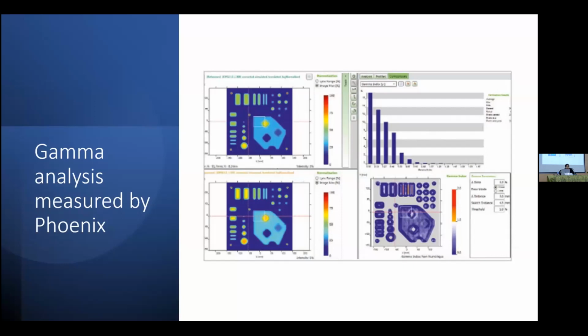Here's another one for QA. This is also measured by the Phoenix. What this helps with is when you're now delivering a certain pattern. The machine is delivering a certain pattern, so how effectively is it delivering that pattern? You could do these. This particular system, the one shown within the Phoenix, has different things inside of it. So you could deliver and check the edges and such, and it has some analysis. What this does is help you understand the characteristics not only on the central axis, but off axis, and also at different dynamic ranges, and also reproducibility. So it's something that you can measure today and then measure next week and make sure that the beam is actually keeping its characteristics the same.